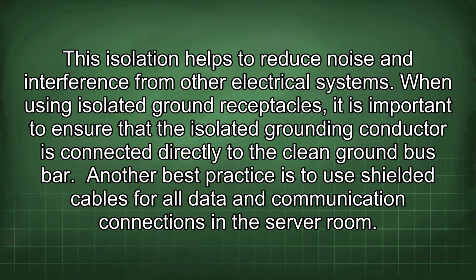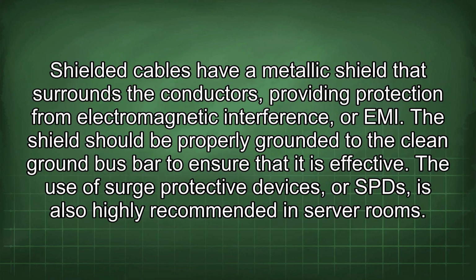Another best practice is to use shielded cables for all data and communication connections in the server room. Shielded cables have a metallic shield that surrounds the conductors, providing protection from electromagnetic interference, or EMI. The shield should be properly grounded to the clean ground bus bar to ensure that it is effective.